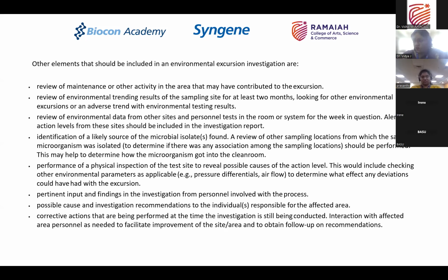If on the countertop or on the floor you get more than 100 CFUs, then you will call the cleaning person, or you will recommend, put a tick for cleaning, that the room has to be cleaned immediately. That's how you do it in the industry. So immediately clean the room, clean the area. After cleaning is done, you'll have to do the review again. Review is nothing but taking the swab wherever the area has been cleaned and checking for growth.